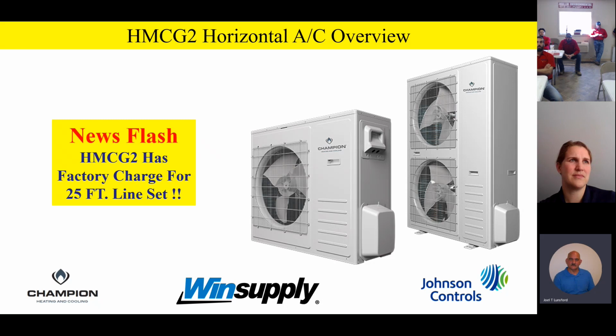In addition, kind of a little news flash, the HMCG2 has a factory pre-charge on the outdoor unit for a 25-foot line set. Now, this is kind of different. Most of our Champion residential equipment, with the exception of this, is pre-charged with enough refrigerant for a 15-foot line set. So this product is actually set up with a pre-charge for a 25-foot line set. So that's pretty nice.